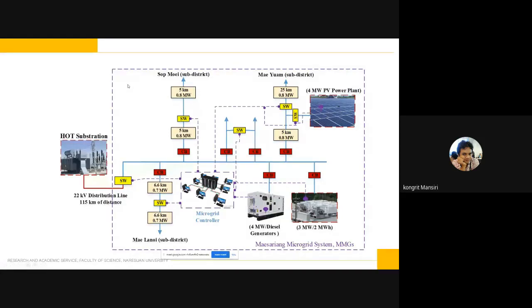So this is the Maesariang microgrid system. It is far from Hot substation. Hot is the name of the district, which can connect at 22 kV. The distance is about 115 kilometers, so that is why there is a lot of loss, about 15%. In this microgrid, we have a switch between this substation and the Mansiri substation. Inside, normally we have 4 megawatt diesel generators, but they will install a 3 megawatt battery storage with a capacity of 2 megawatt hours. Yes, you can see from this photo, it's big.